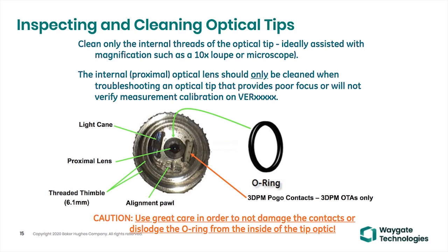Yep. So the question is, when you're cleaning an optical tip adapter, this would be a measurement tip. She's asking about the pins, and the question was about cleaning the pins and whether that was during cleaning and how you safely do that. Yes. Good. Okay. So what you're looking at on my screen is the ID, or the proximal body of a 3D phase measuring lens.